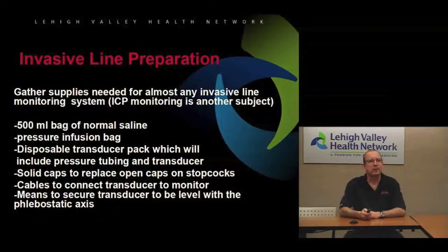For invasive line preparation, it's basically starting from scratch. Before you even get started, you'll need to gather all your supplies for your monitoring system. So there'll be a 500 bag of normal saline, pressure infusion bag, disposable transducer pack, which will include both the pressure tubing and the transducer, solid caps to replace the open caps on the stopcocks. Usually the solid caps will be included in the trans pack or the transducer kit.